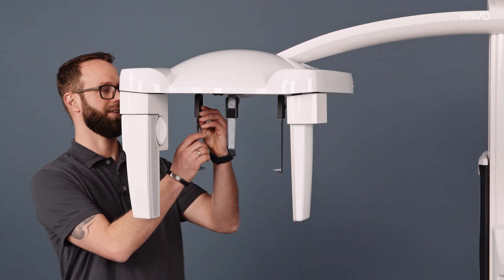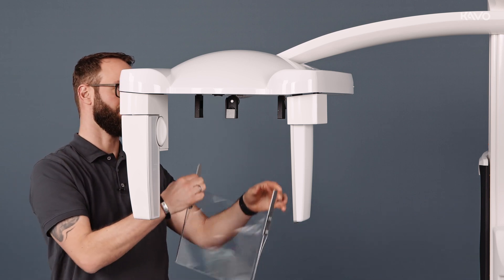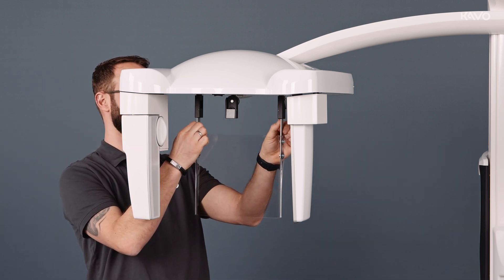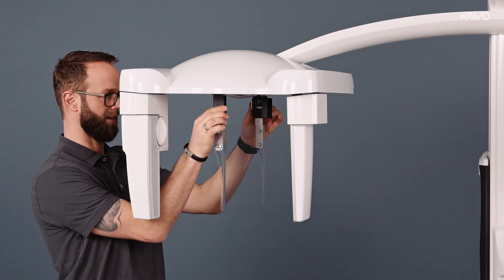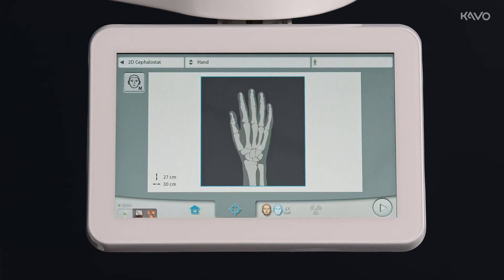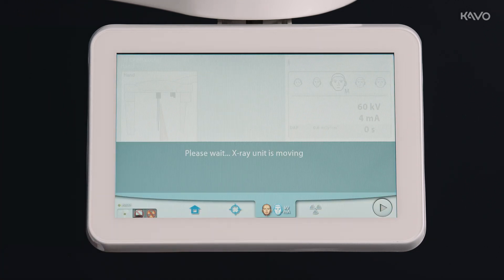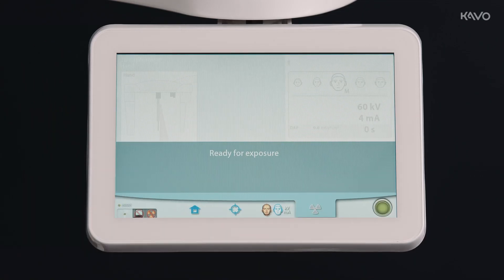To create a hand image with the Ceph unit, we first disassemble the headrest and nasion, and attach the handcarpus plate. After that, we rotate the frame in the handcarpus plate. We now select hand on the display and go to the positioning level. Now we can position the patient's hand on the handcarpus plate, go into image ready mode and perform the imaging. Further details of the KaVo Pro XM 3D and Romexis are available on the KaVo website, in the other videos and in the instructions for use. Thanks for watching.